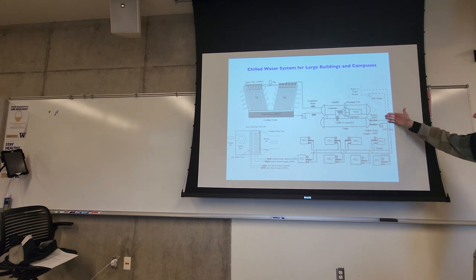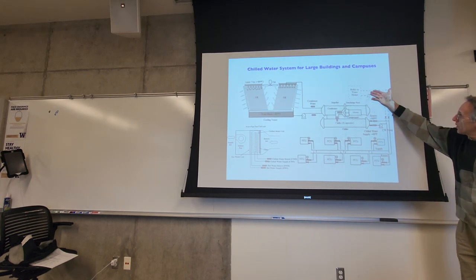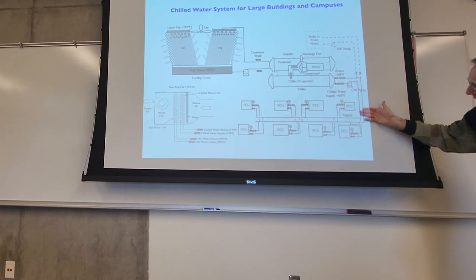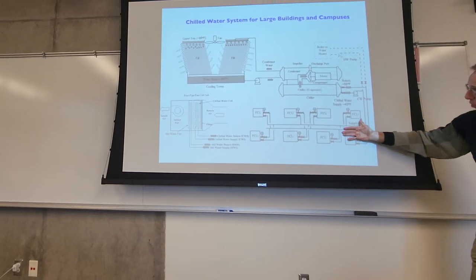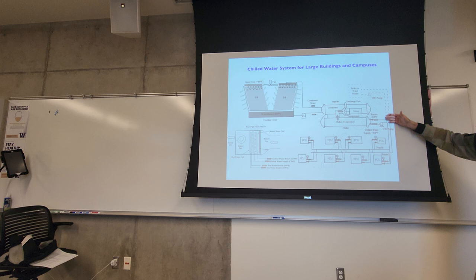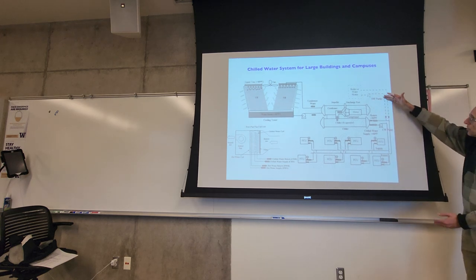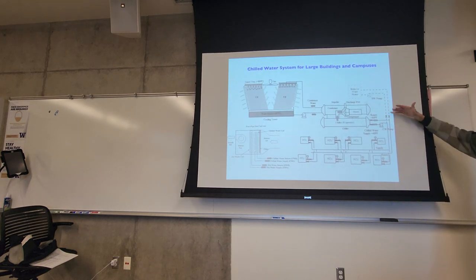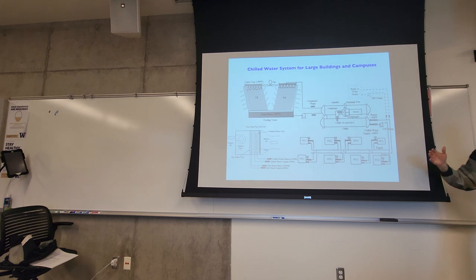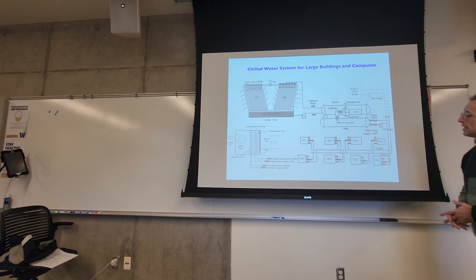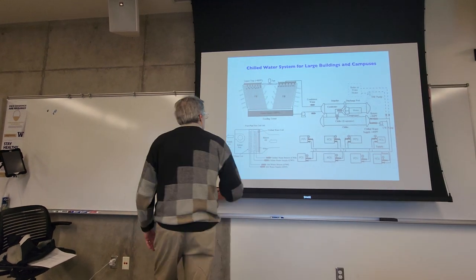And this one is set up so you can actually pipe in the hot water when you need it, taking advantage of the same pipes as the cold water. Except the downside here is you can't have simultaneous heating and cooling. You can have one or the other. But a lot of buildings today, you have heating and cooling going on at the same time. Some spaces might be heated while other spaces are being cooled. And so the four-pipe system gives you more versatility.